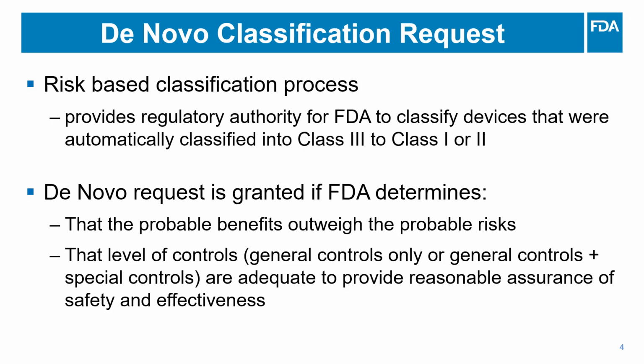The de novo review is a risk-based classification process. During this process, FDA assesses the data and determines if the probable benefits outweigh the probable risks and the level of controls needed. If the de novo is granted, it establishes a new device type along with a new classification. Also, if the de novo is granted, the device is eligible to serve as a predicate for new medical devices where appropriate, following the 510K process.